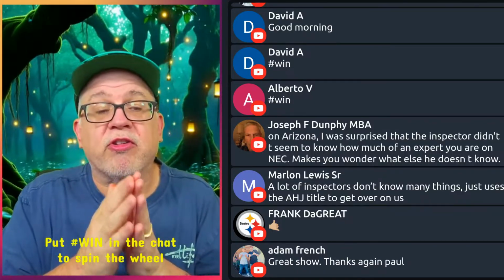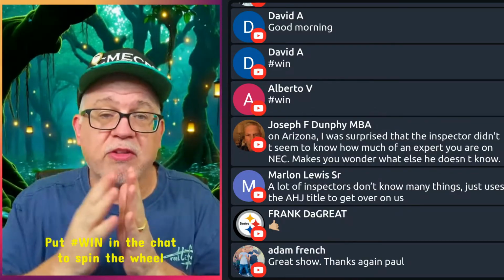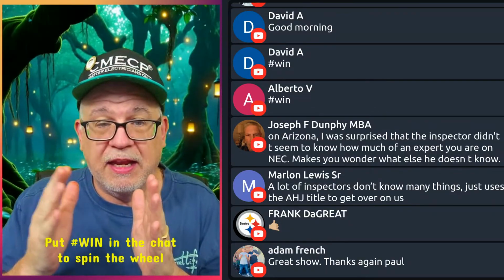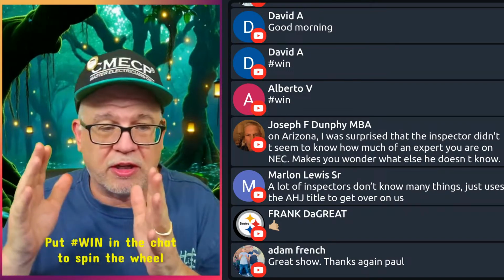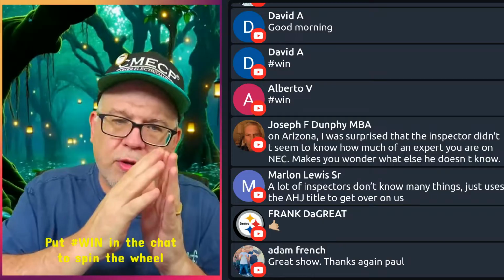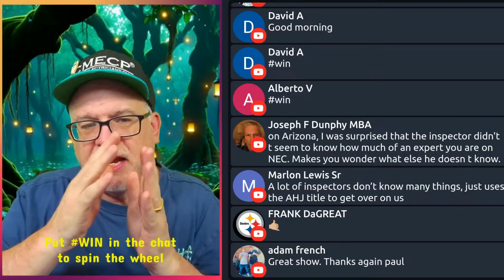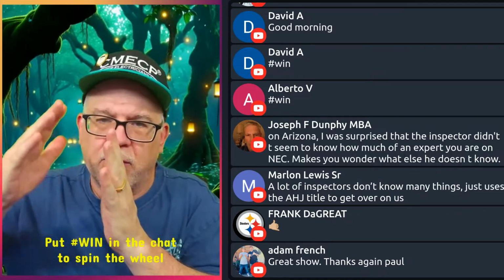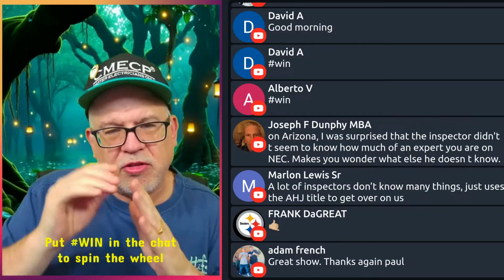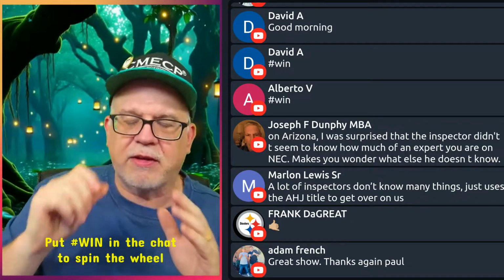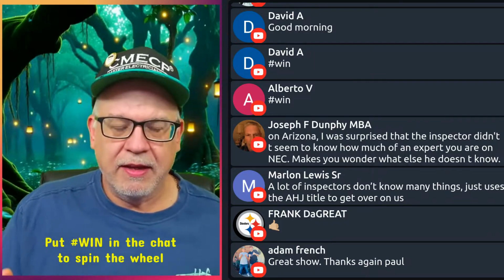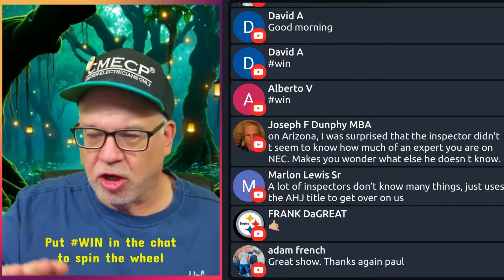That is why breakers come in different trip curves, because there are applications where there is a delay, and that's where we start looking at selective coordination and when something trips. We don't want it to trip too soon because we understand that it could get into this area, and we don't want it to trip until it gets here. So you start looking at these curves and make sure you fall nicely in there, that type of thing. You know what I'm saying? So at the end of the day, follow the nameplate. It's going to be fine.